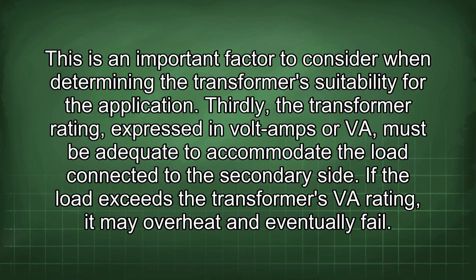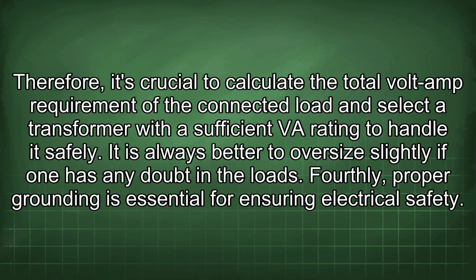Thirdly, the transformer rating, expressed in volt amps or VA, must be adequate to accommodate the load connected to the secondary side. If the load exceeds the transformer's VA rating, it may overheat and eventually fail. Therefore, it's crucial to calculate the total volt amp requirement of the connected load and select a transformer with a sufficient VA rating to handle it safely. It is always better to oversize slightly if one has any doubt in the loads.